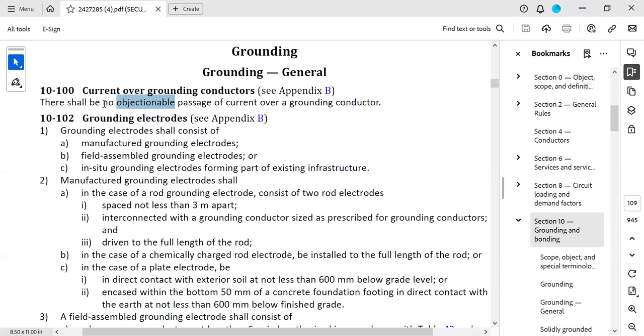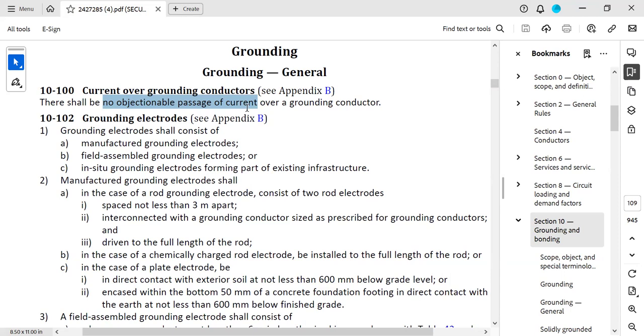If you do find an objectionable passage of current in a ground conductor, then one or more of the grounds in the neutral conductor should be removed, or the location of those grounding connections has to be considered and moved, or the continuity of the grounding conductor between grounding connections should be interrupted.